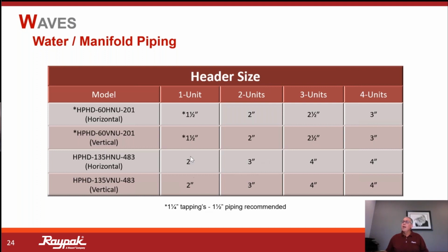Now, be aware that these smaller units, these 60,000 BTU units, they come standard with 1.25 tappings. That is our tapping size at the unit. But we are recommending 1.5-inch piping. So right away out of the gate, we're going to be converting over from 1.25 to 1.5 in single unit applications. In multiple units, we just pick the number of units and the size of the heat pump, and that will dictate then what header size we will be using.